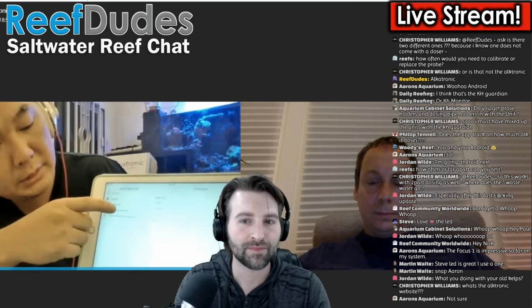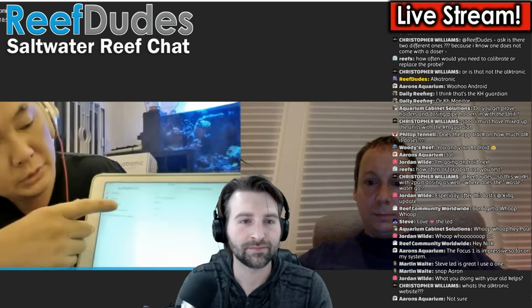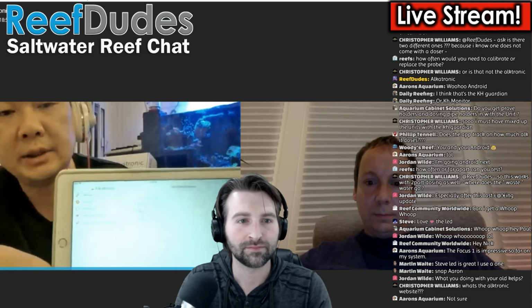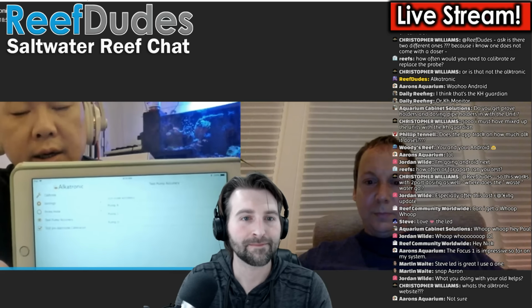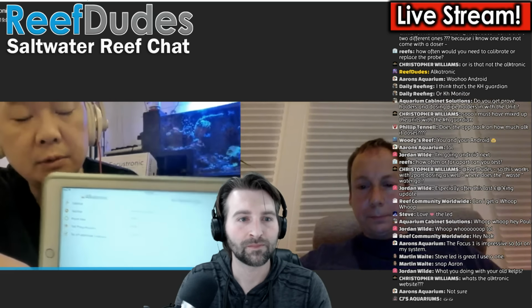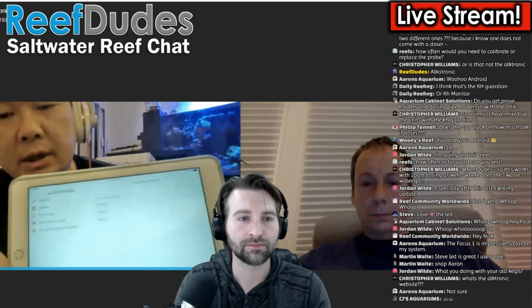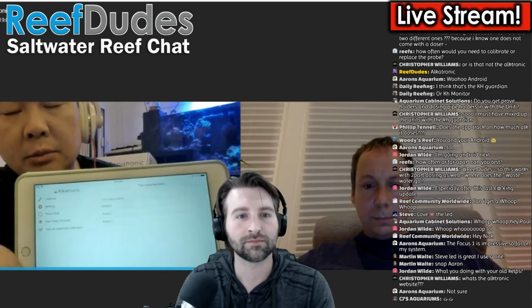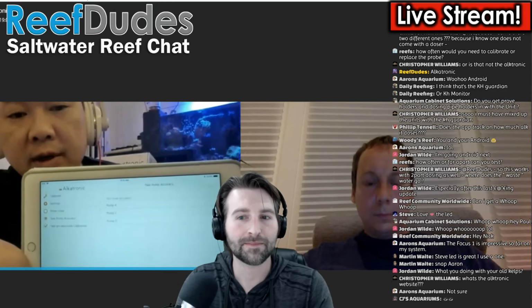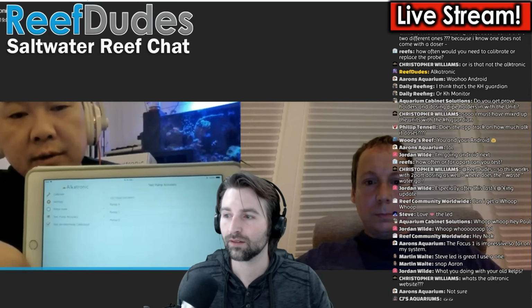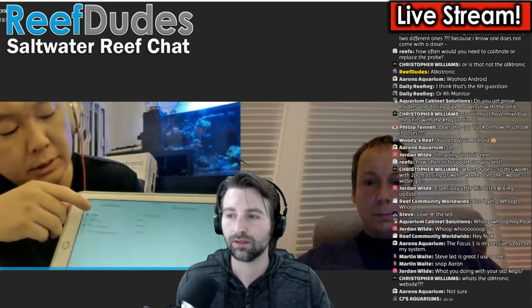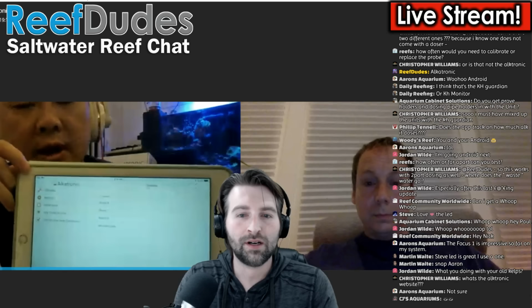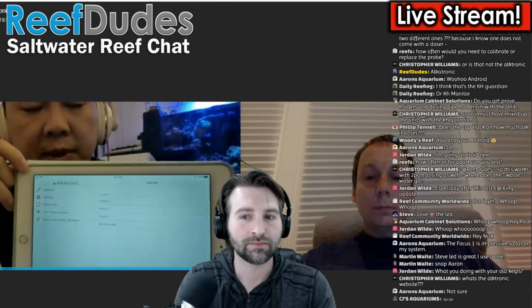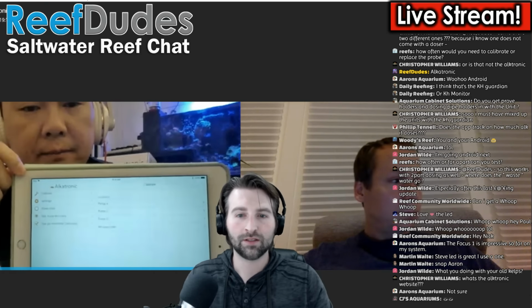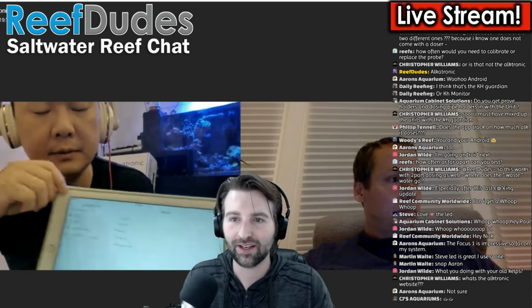And this button allows you to test the accuracy of the pumps, and the bottom one will let you do the pH, not calibration, but also test the pH probe to see if it has drifted. And then the first button is the calibration, where you do all the calibration for the pumps and the pH probe. Okay, excellent. Thank you for that.